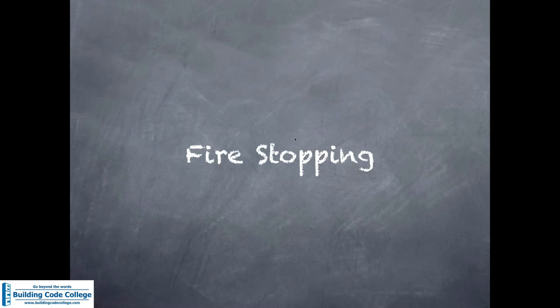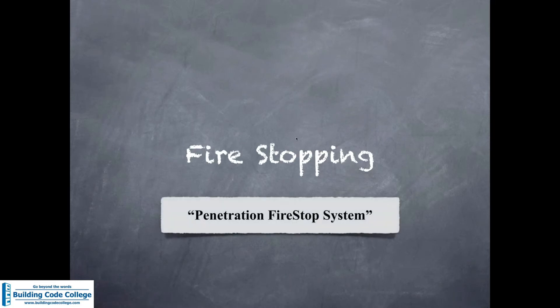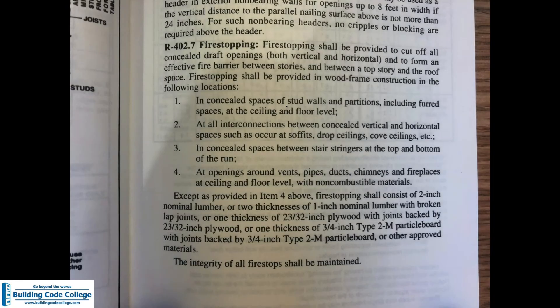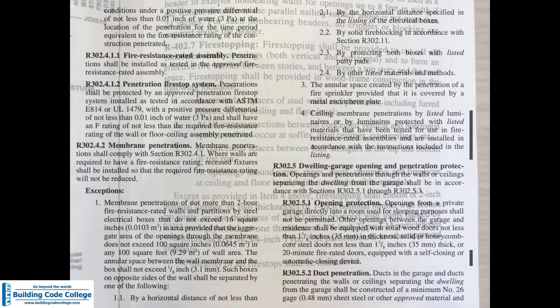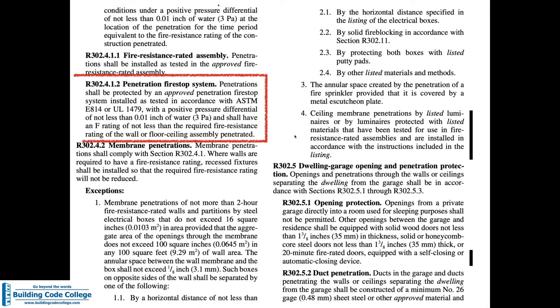Fire blocking is now what fire stopping used to be. So what's fire stopping today? In today's code it's called penetration fire stop systems — not just fire stopping. It is a tested and listed system that you install. Here's one of the last code books that used the term 'fire stopping' with a description that actually described fire blocking. And in the 2018 IRC you can see the section for penetration fire stop systems, which is completely, 100% totally different and unrelated to fire blocking.